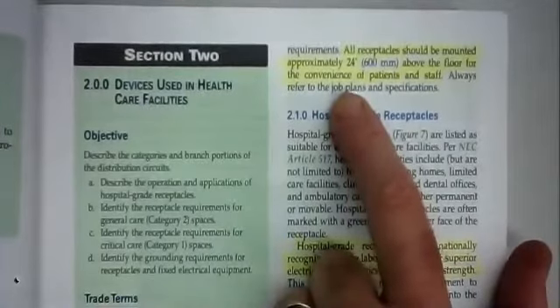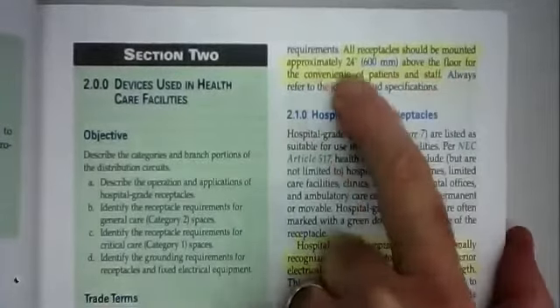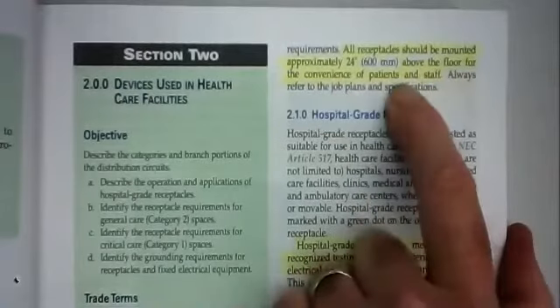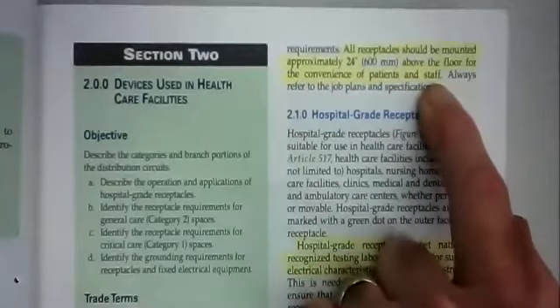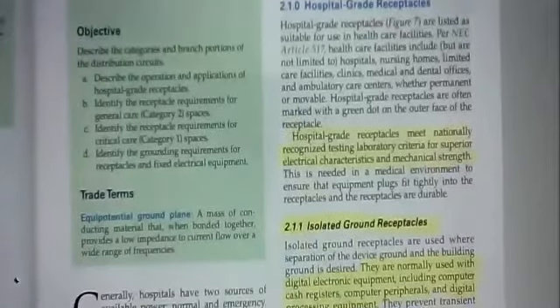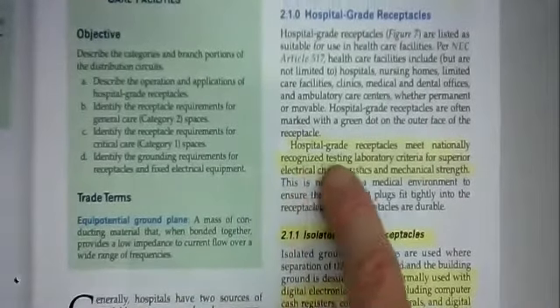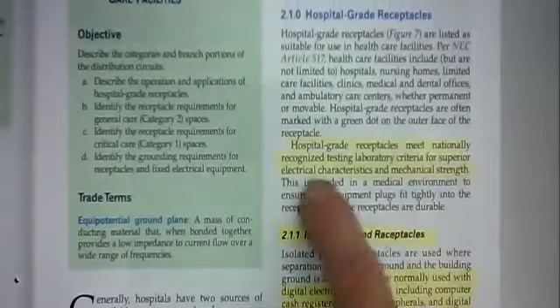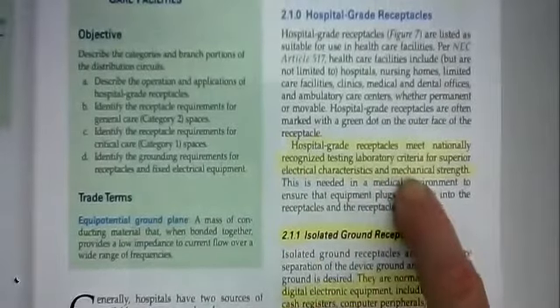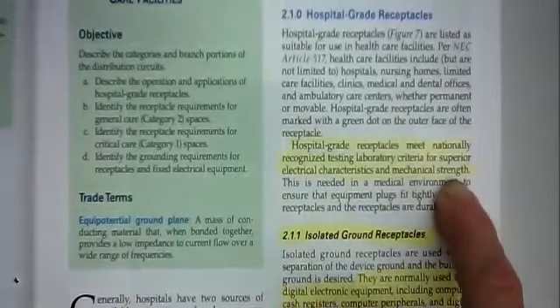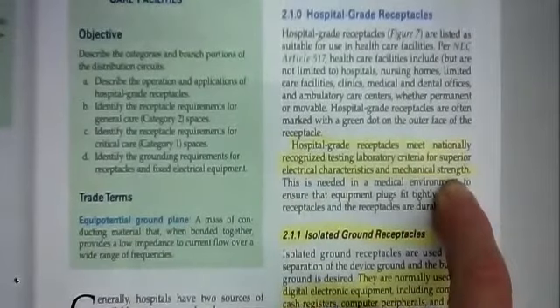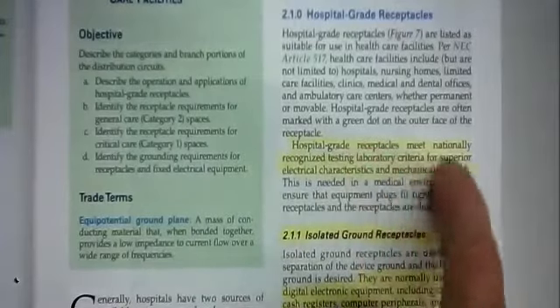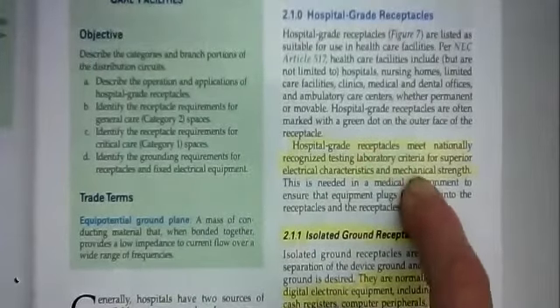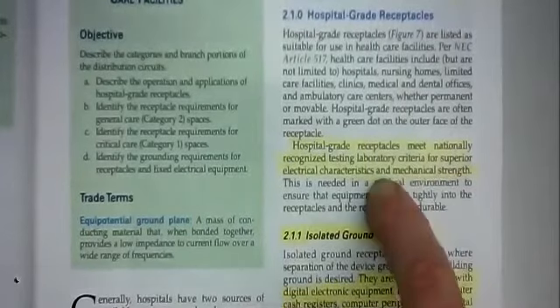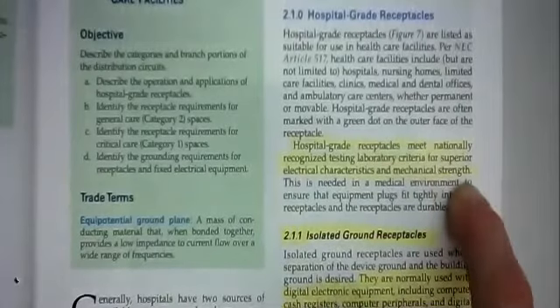So here on the right-hand column of page 11, it says all receptacles should be mounted approximately 24 inches above the floor for the convenience of patients and staff. We're not going to put them at 12 inches. Hospital-grade receptacles meet nationally recognized testing laboratory criteria for superior electrical characteristics and mechanical strength. If you ever buy hospital-grade receptacles, you'll see that when you try to plug something in, you have to really put some force behind it to plug it in. That's because they want it to take a lot of force to unplug it as well.